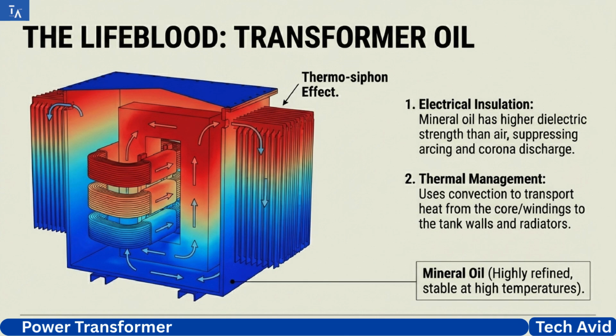This mineral oil is a multi-tool. First, it's an insulator, far better than air, preventing arcs and corona discharge. Second, it's a coolant. Heat from the core and windings is absorbed by the oil, which rises via convection, passes through radiator fins to cool, and cycles back down. This is a closed, life-sustaining loop. Keeping it cool is non-negotiable because paper insulation degrades irreversibly with heat.